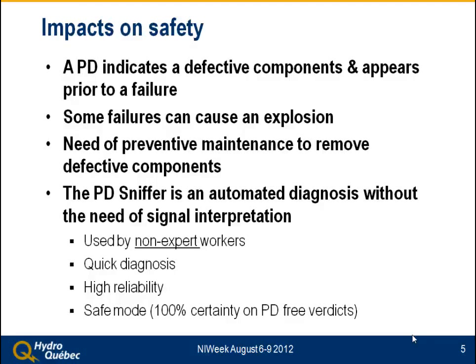It has to be a quick diagnosis, highly reliable, in a safe mode with 100% certainty. That means we want to be sure that if we say there is no PD, there really is no PD. We can be wrong if we say there is one, but we can't be wrong if we say there is none. So everything is made to have a safe mode, but we don't want to raise too many false alarms either. That's why it's been a long development - a lot of signal analysis, conditions, etc.